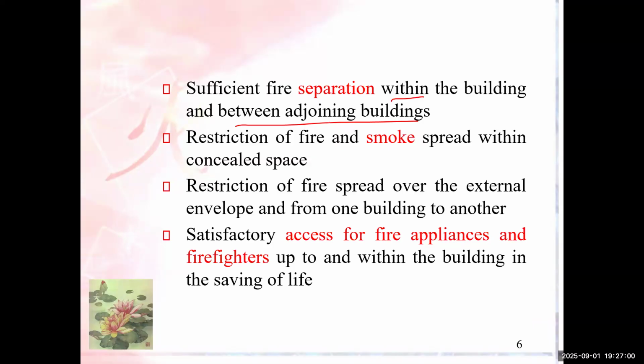Restriction of fire and smoke spread within concealed spaces: the concealed space inside a building may affect fire behavior when a fire breaks out, for example in the compartment of origin, or the space above the suspended ceiling, which may contain services like ductwork, cables, and trays. Restricting fire and smoke spread within the ceiling void, wall cavities, and surface ductwork is important for effective fire safety.